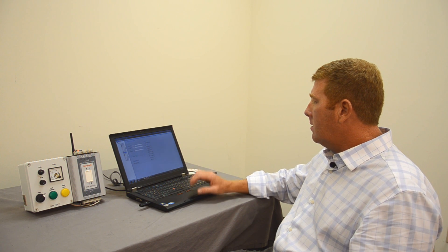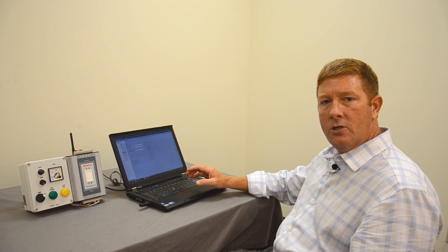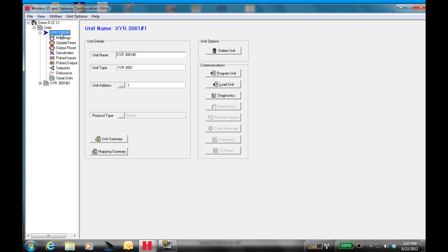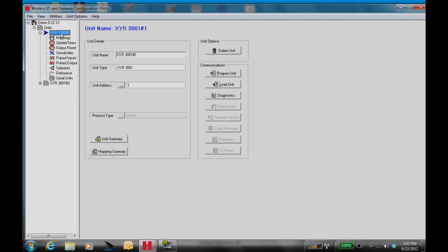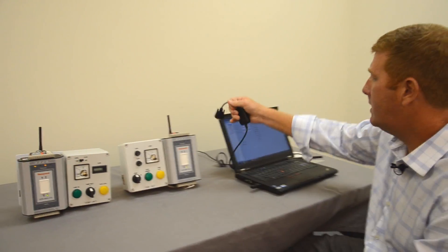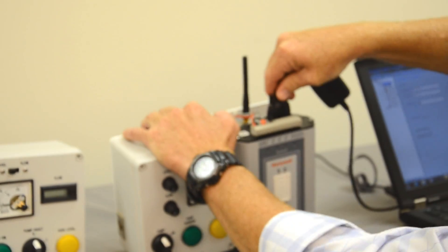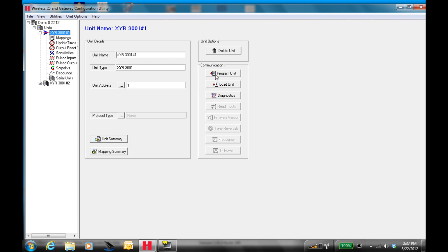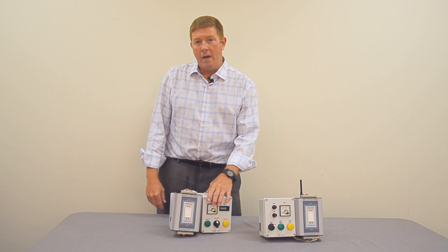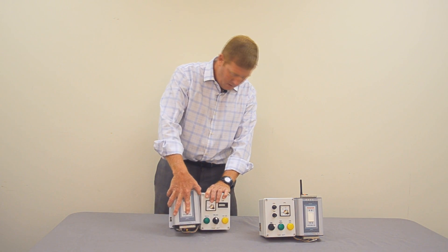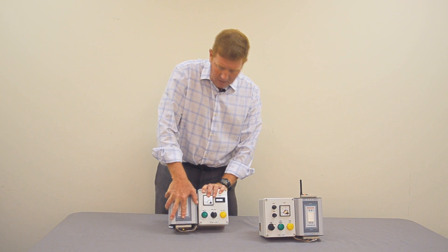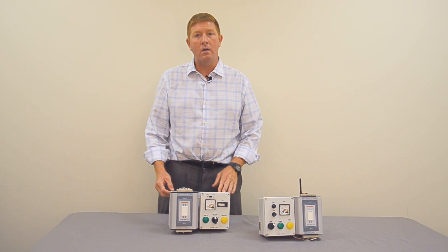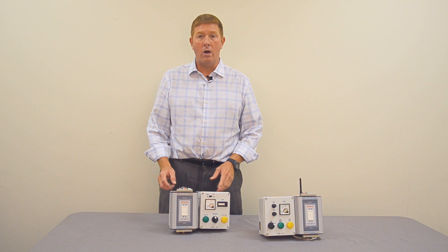Once your mapping is complete, you want to load your configuration into each associated radio. To do that, you click on the radio you're about to connect to, which in this case will be unit number one. We need to serially connect from our PC to radio number one. Make sure we have radio one highlighted, click this tab, and it will write your configuration to that unit. Once your mapping is complete and your configuration is loaded into each radio, you can then mount your units in the field, tie in associated wiring, and watch your product work for you.